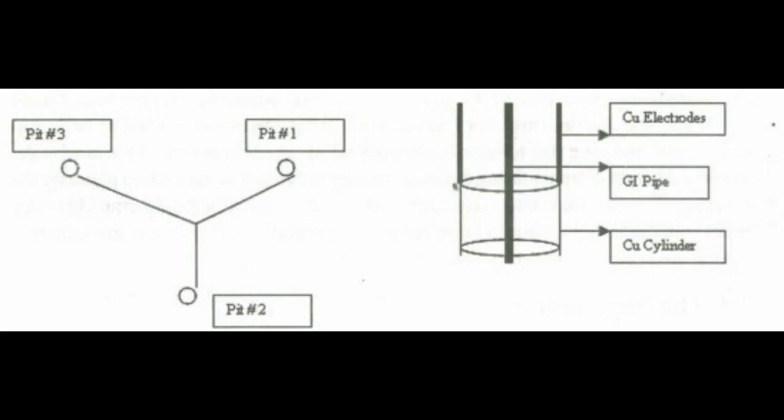In terrains such as deserts, rocky soils, hilly regions etc., where it is difficult to attain low earth resistance, one can add bentonite with charcoal and salt. This gives much better results. A much more sophisticated way is to create a grid of 3 earth pits and join them to achieve still lower earth resistances. Once again, the choice depends on the availability of finance. Design for construction of earth pits is as below.